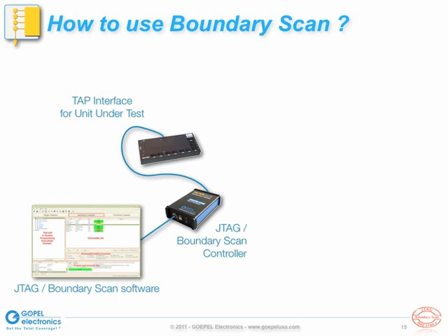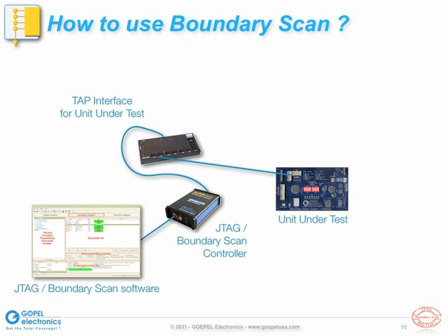The TAP interface hardware is connected to the UUT's test bus connectors, providing test access to the TCK, TMS, TDI, TDO, and TRST signals. TAP interface hardware may provide a number of TAPs for connection to multiple scan chains, as well as additional test resources such as digital and analog I/O.